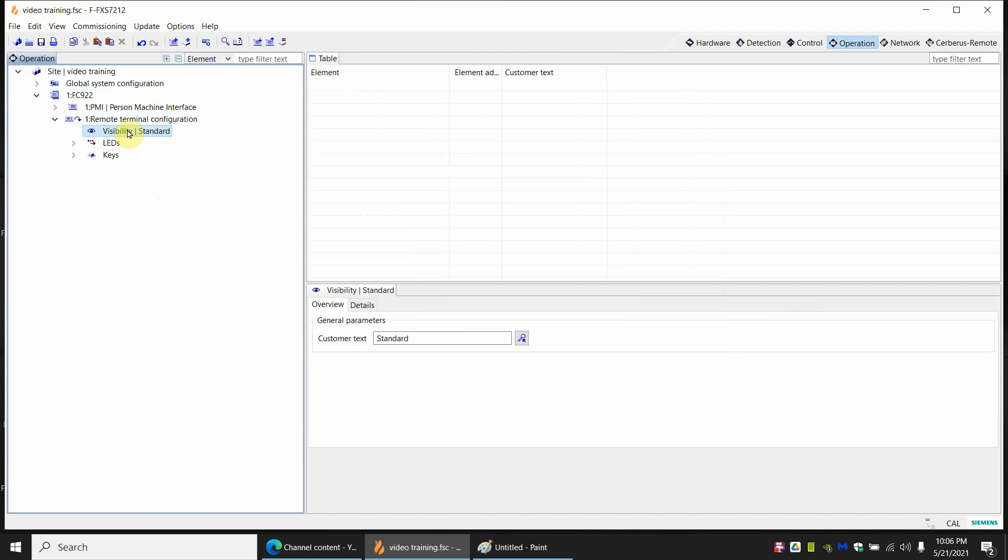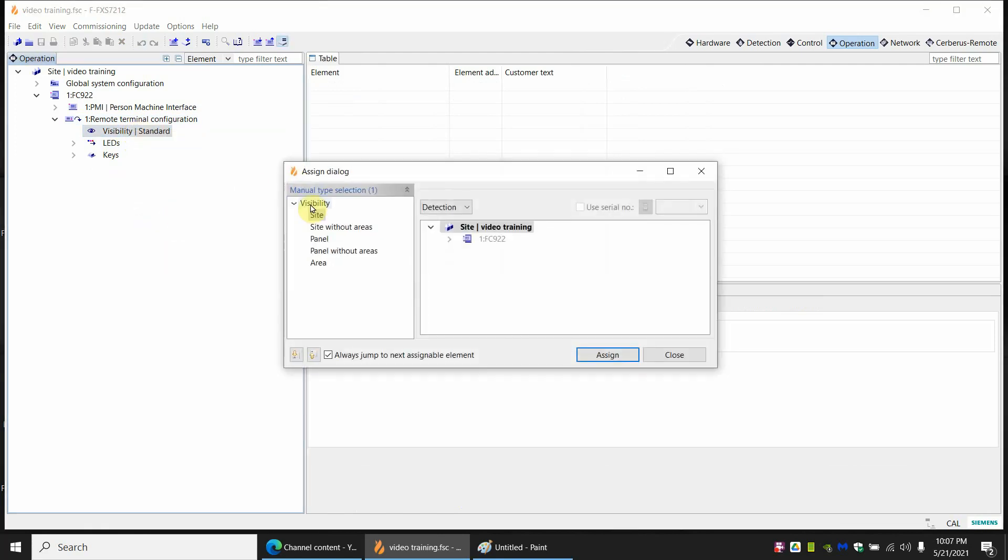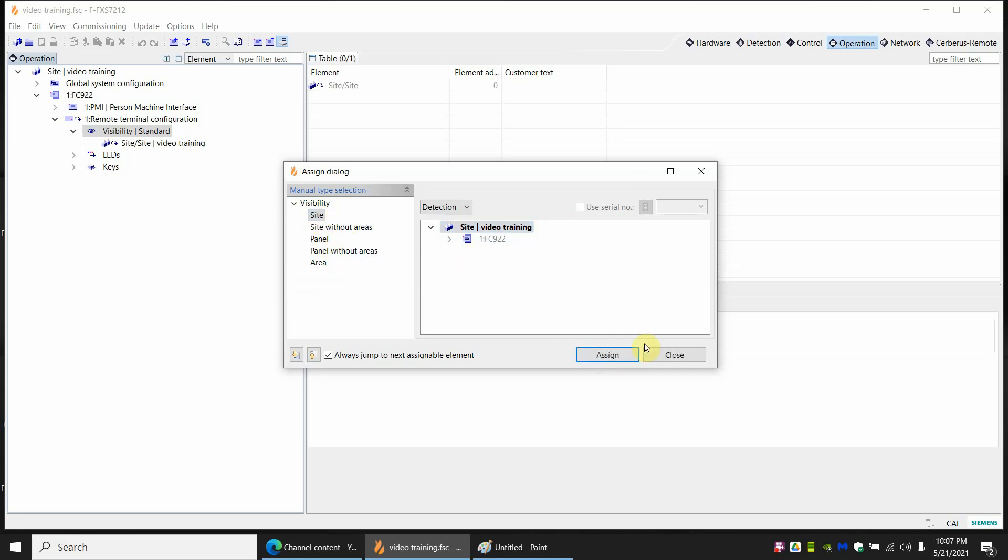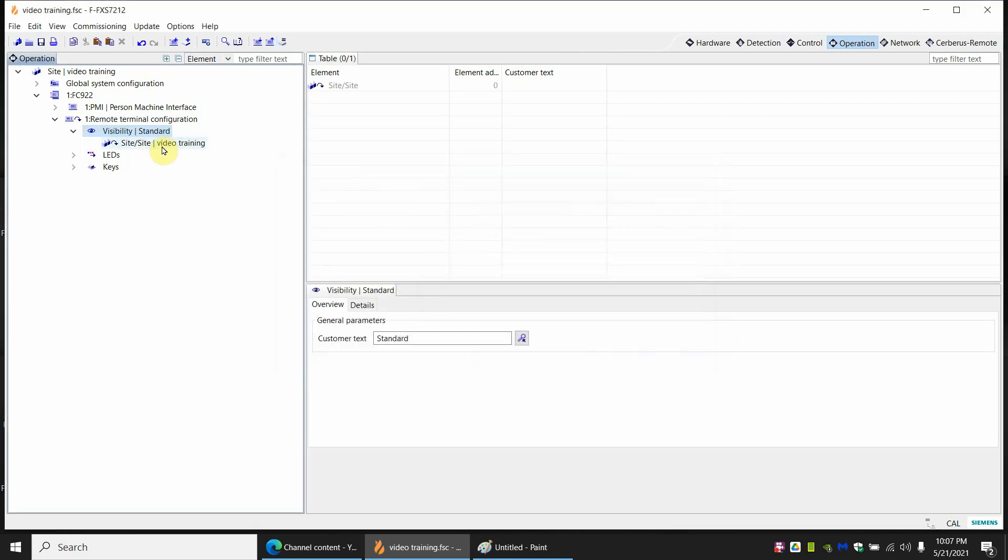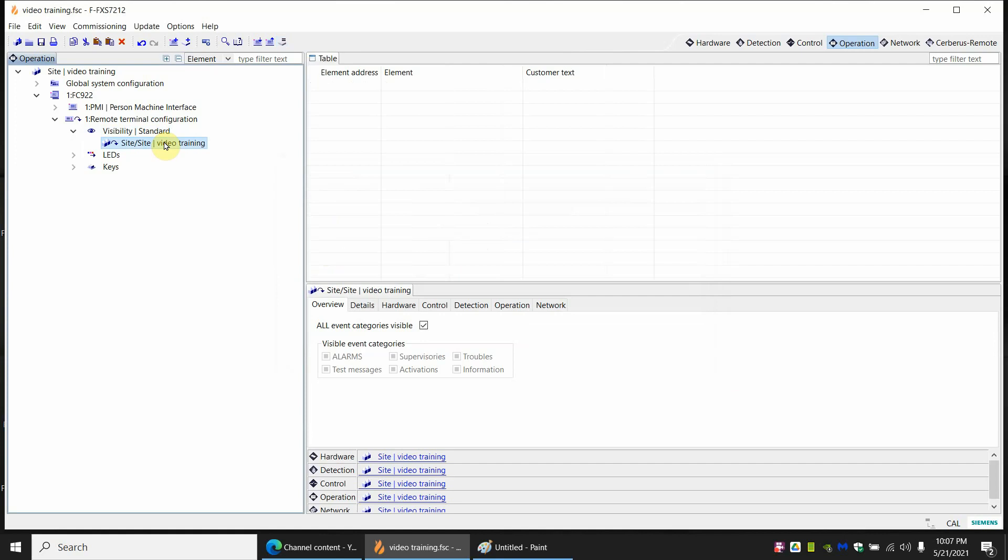Now at this point it's still not doing anything for us because we still haven't told it what do we want to see here. For that we have visibility. If I right click on visibility and hit assign, I can say just show me the entire site. And what that will do is if we have one panel or 20 panels, it doesn't matter. It's going to show us everything. In this case since we'll have one panel it doesn't matter if we pick site or panel. It's the same thing. You can limit it down to a certain area. Again if you have a high-rise building with 20 floors and you want this annunciator just to show floors one through four, you can select that. But in this case I'm just going to pick the site.